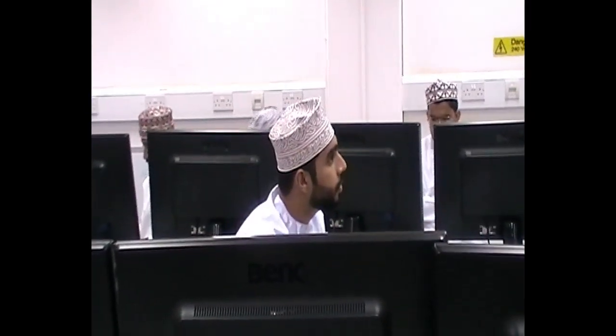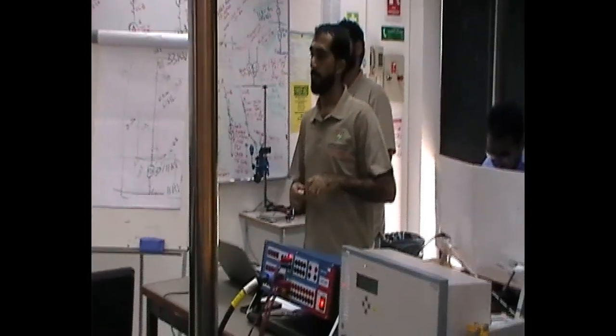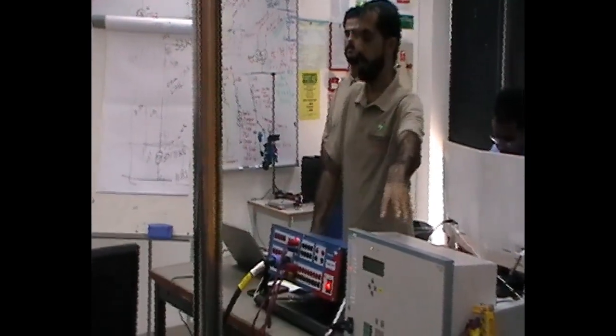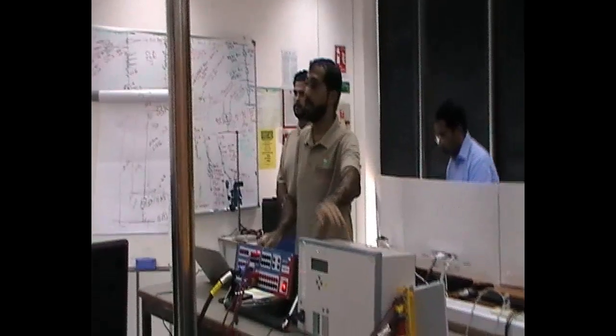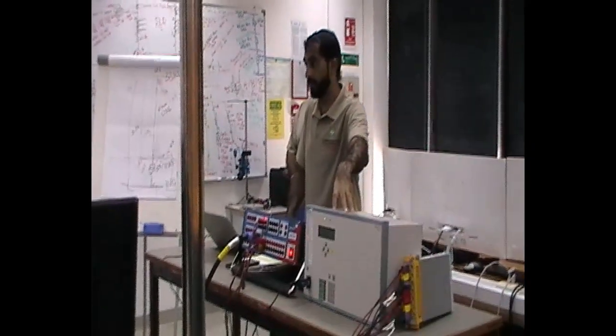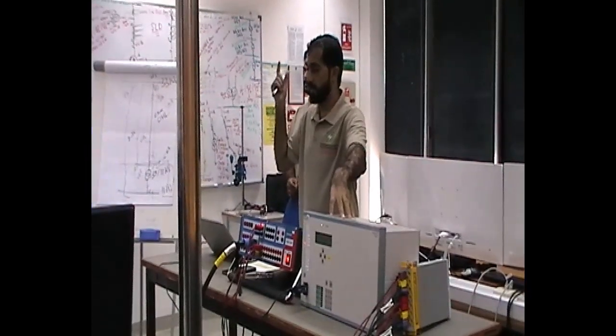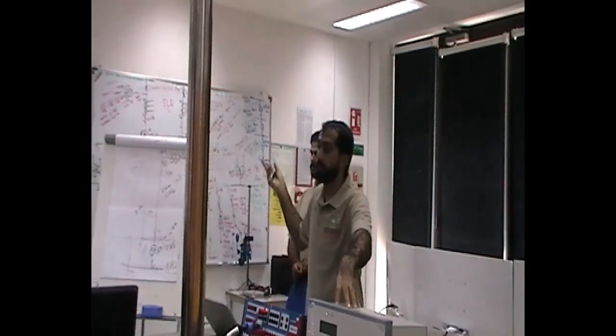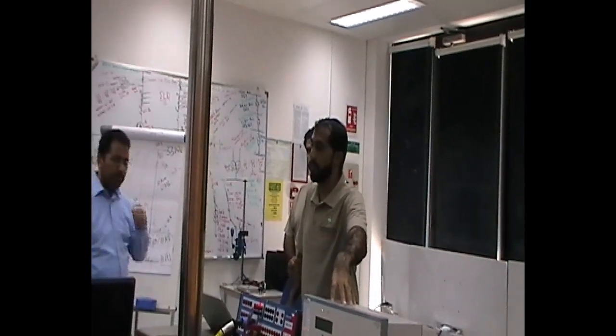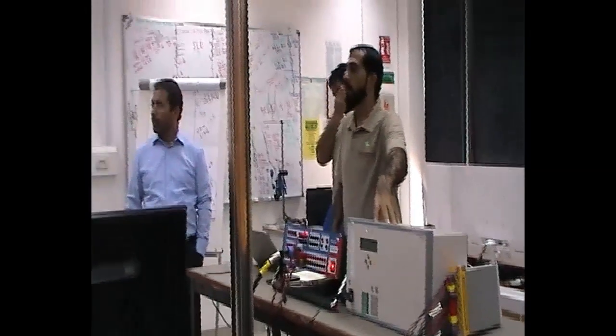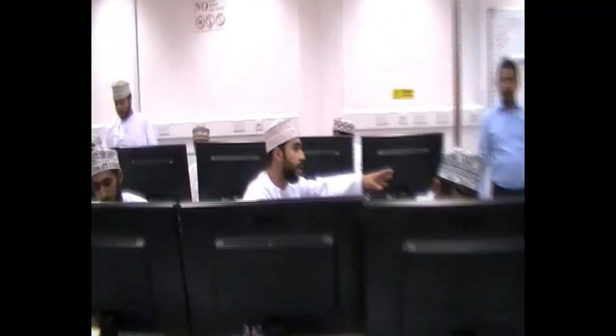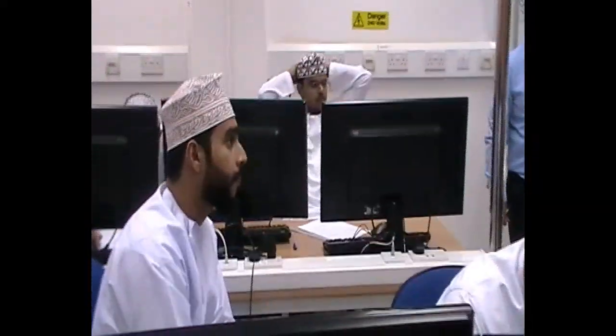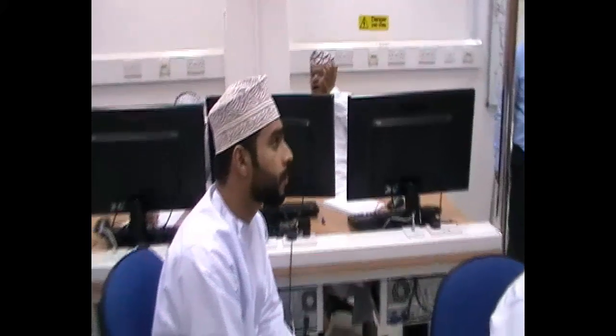You can set the time delay to another, I can change the time, and you can put it the same. Whatever I change here, I could take it and put it in the test kit. I can change anything I want in the relay in terms of setting, meaning reach and time. I could go to zone 2 with some time delay, zone 1 with some time delay. It's configurable. But in the relay itself, it's not depending on the distance. The time will depend on the zone, whichever zone is covered in the fault.